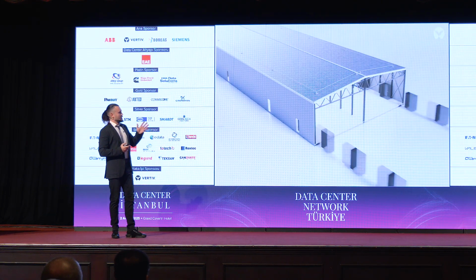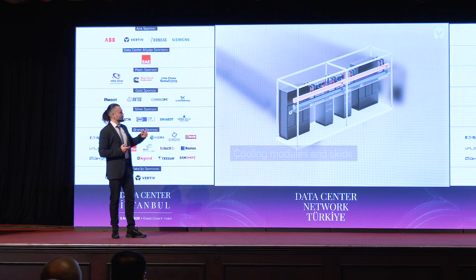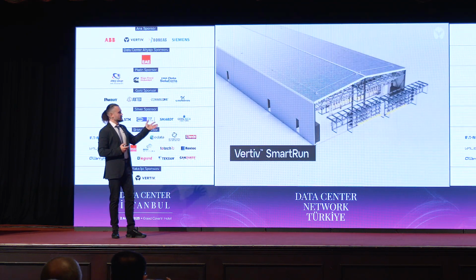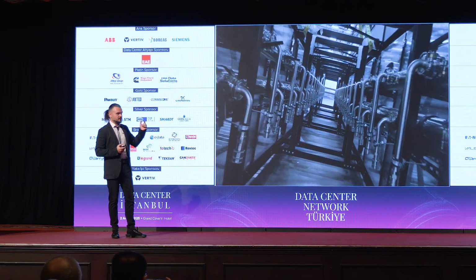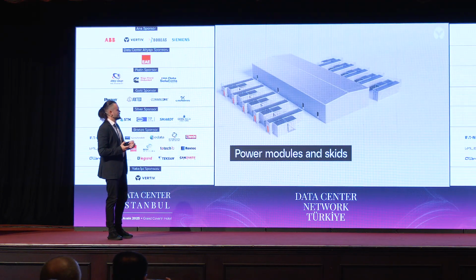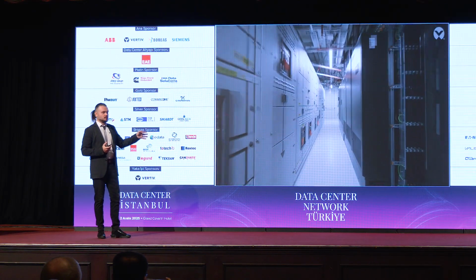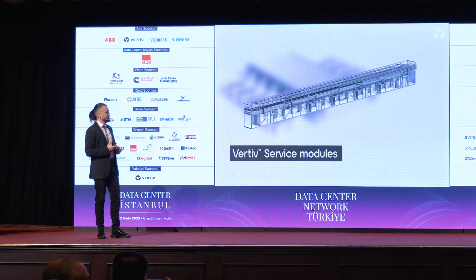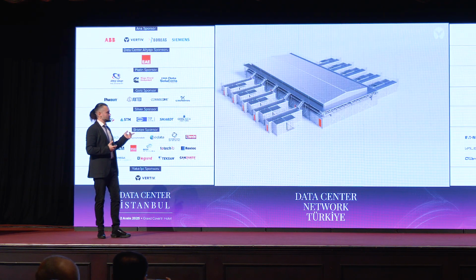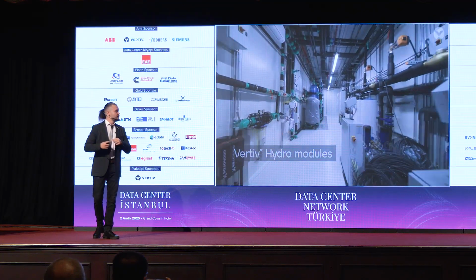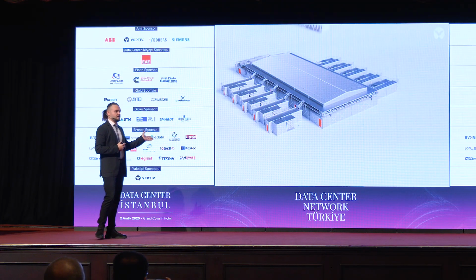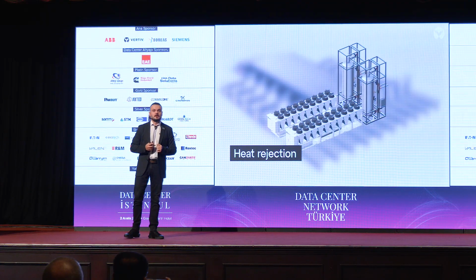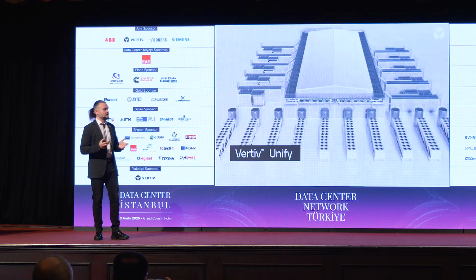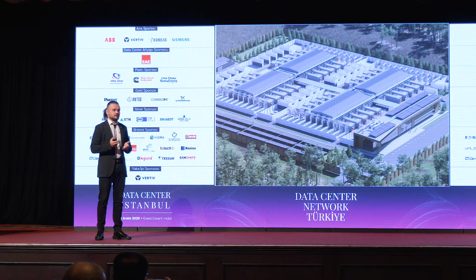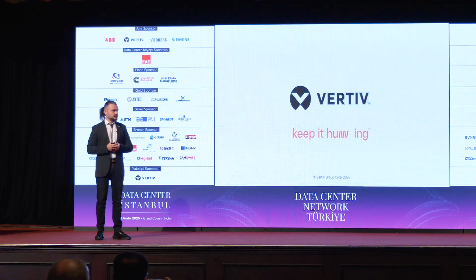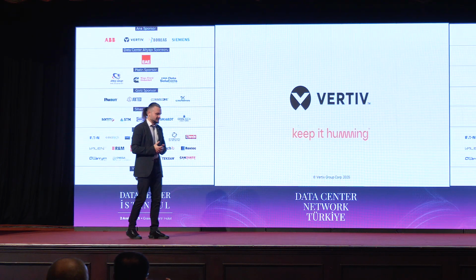It's a shell. We have the fan coil units inside, brought prefabricated on skids. We have the structure to accommodate the bus bars, secondary fluid network, CDUs, and racks if needed. Outside, we are putting the power modules with medium voltage and low voltage powertrain. We are providing so-called service modules just to connect one thing to another. And we have the hydro modules and specially developed chillers, which we call trim coolers, which operate at very high temperatures because the temperature regime inside the secondary fluid network can be above 40 degrees Celsius. That's a short video, just a teaser for you.